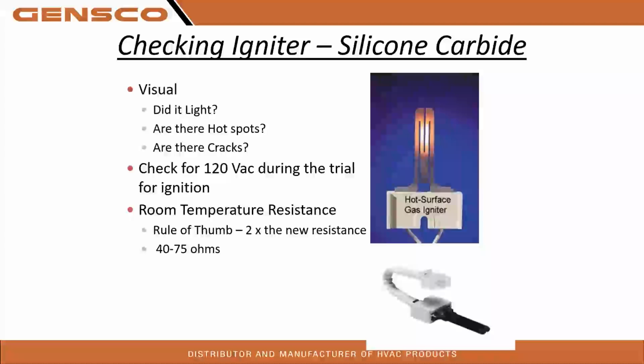So we're going to look at how igniters light, right? It doesn't matter if it's 80 volt or 120. You're going to visually check it out. You always want to unplug an igniter when you're moving it, even if it's not calling, because there is some voltage there. Especially in some manufacturers' product, Rheem comes to mind. If you take that igniter out while it's just sitting there idle and you do not unplug it, you can do some damage to the control board. Certain models, hopefully they've resolved that issue. So you always want to unplug igniters whenever you're moving them around, because if you tap them to sheet metal, there may be some voltage there. It may do some damage to the control board or the igniter itself.